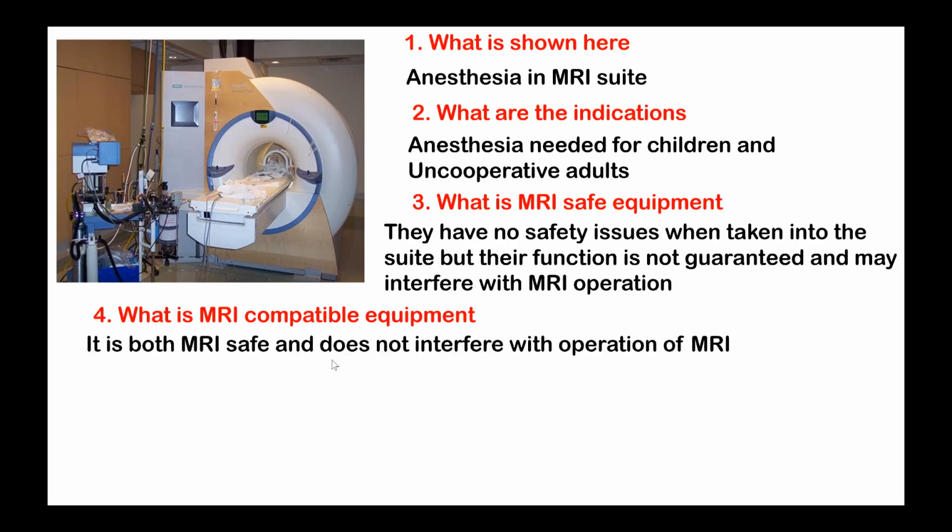Whereas MRI compatible equipment is both MRI safe and does not interfere with the operation of the MRI as well as of the equipment. That is called compatible. So the main difference is, MRI safe equipment will not physically get attracted towards the magnetic field, but it may interfere with the MRI operation. Whereas MRI compatible equipment will not be attracted by the magnetic field and will not interfere with the MRI operations also.